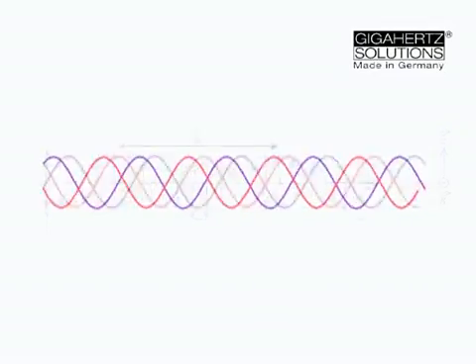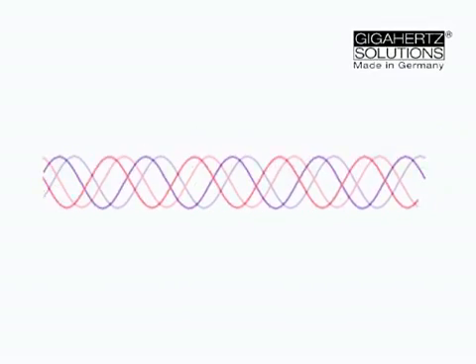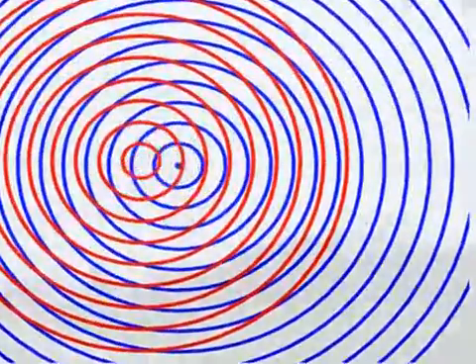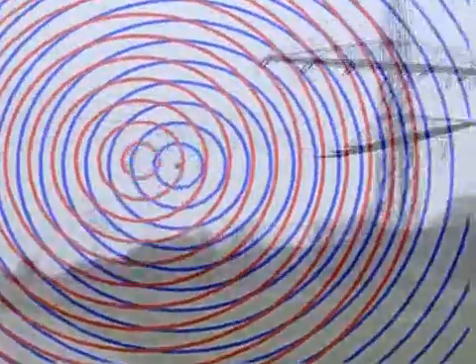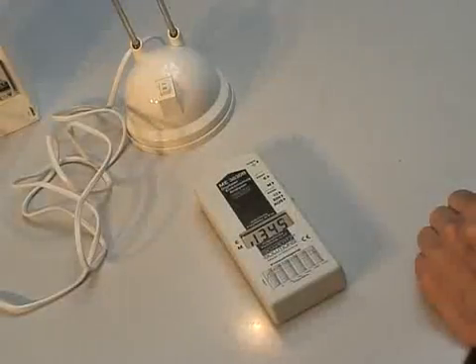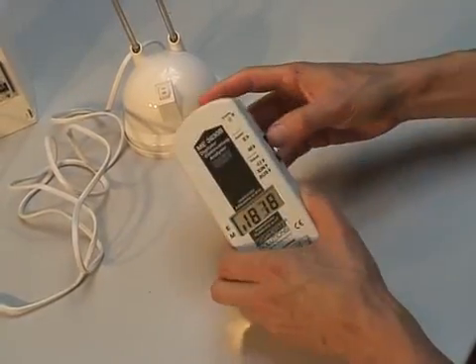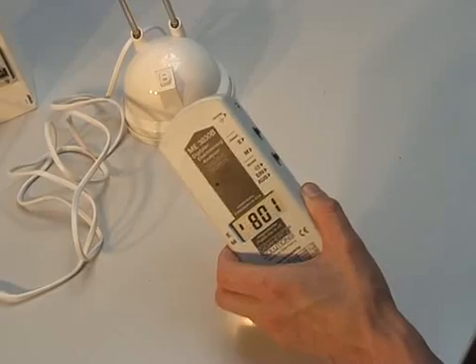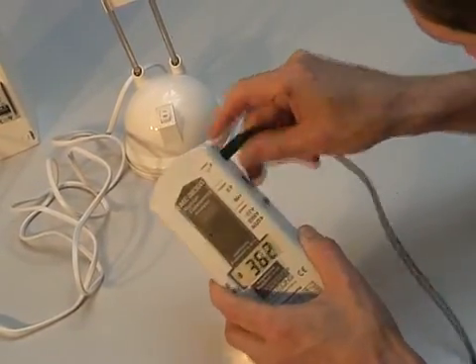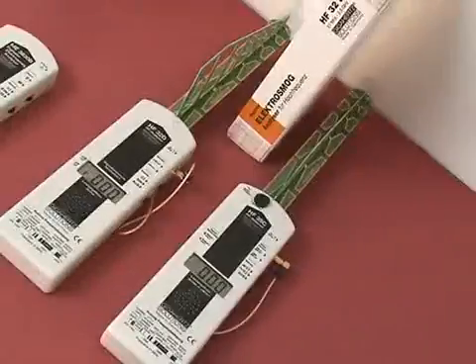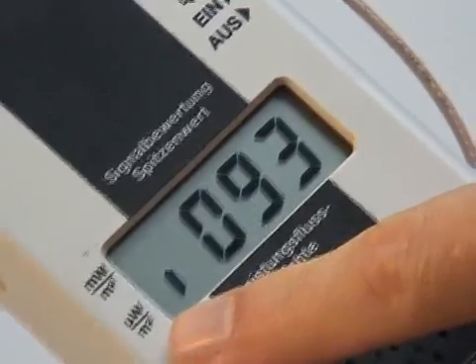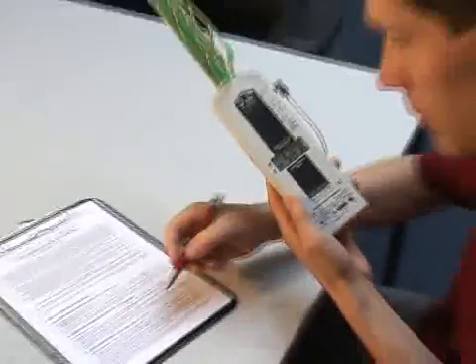In the low frequency, the physical characteristics of the respective spreading properties, at varying distances to the source, make it necessary to individually measure each wave. This means the magnetic field and the electric field must each be individually measured using a low frequency measuring device allowing for both. In the high frequency, the power flux density of the complete electromagnetic wave is measured with a high frequency meter.